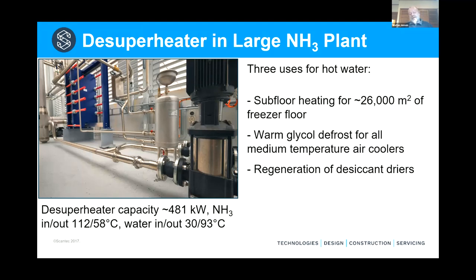So on one side of that little heat exchanger, we've got the glycol that circulates through the cooler, and on the other side, we have the hot water, and then some valves so that we can, during defrost, generate a closed circuit of warm glycol through the cooler so the ice falls off. And the third use is regeneration of desiccant dryers.